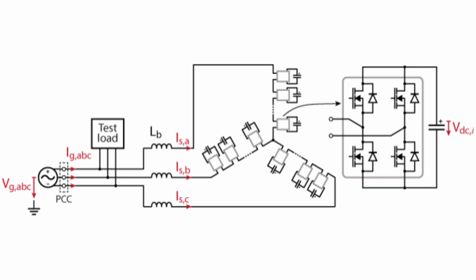When the inverter output voltage becomes higher than the system line voltage, the STATCON behaves like a capacitor. And when it behaves like a capacitor, it generates reactive VARs. That means it supplies reactive power to the system. But when the inverter voltage becomes lower than the system voltage, the STATCON behaves like an inductor. And in this condition, it absorbs reactive VARs from the system. So basically, by controlling inverter voltage magnitude, we can control reactive power flow. This is brilliant engineering.